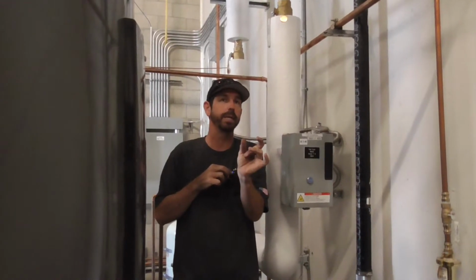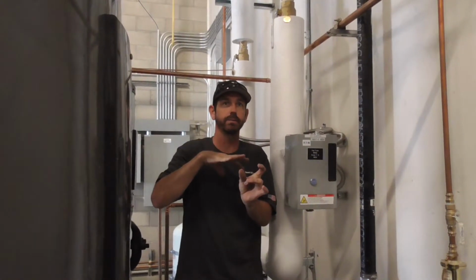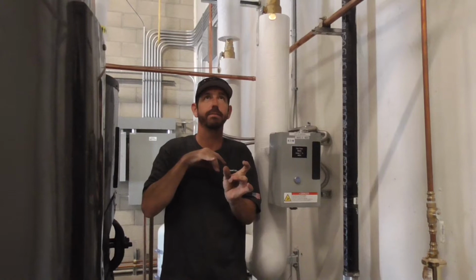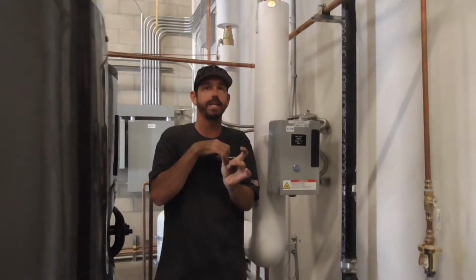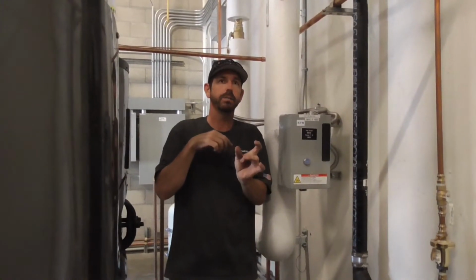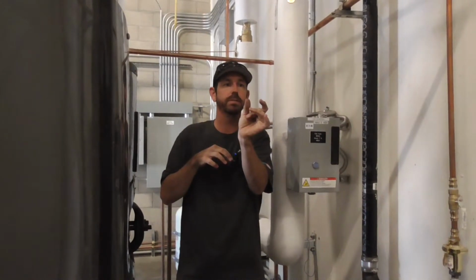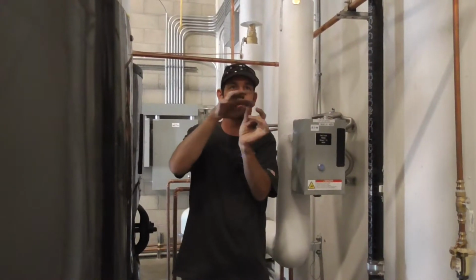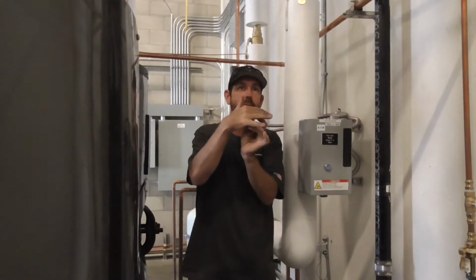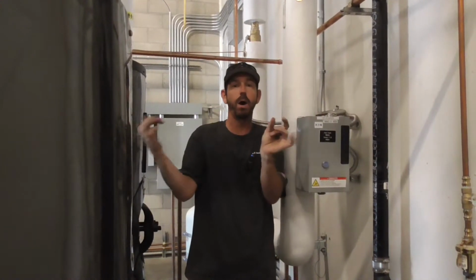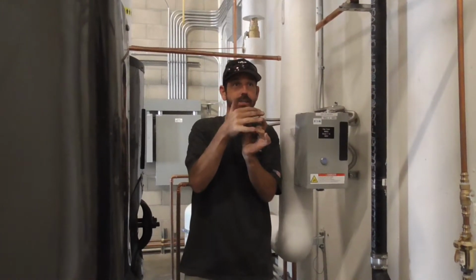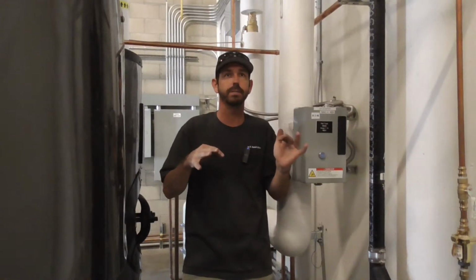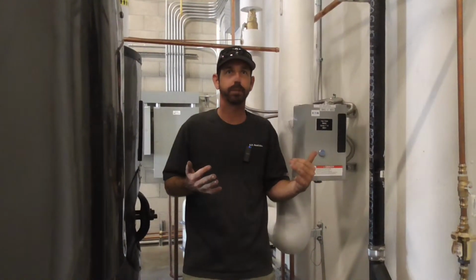105. We'll have to look when we get up there. So there's a temperature setting that they're set to. They're all the way counterclockwise, the lowest setting that we can go to. I think it's actually 105. It's 105 up there and it's 110 down here. Okay? So if it cools off, the bellows shrinks down and the orifice gets bigger, so more water goes through that balancing valve, okay? As that hot water then runs through that balancing device, it expands back out and closes that orifice and lets the water go other places. So it's a self-balancing system, okay?